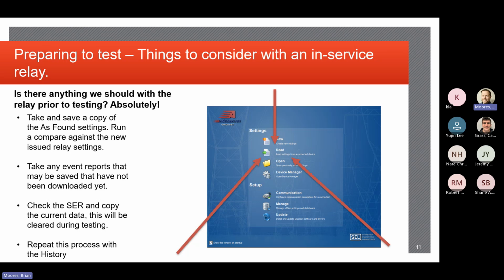The SER data is sort of line by line, text-based, if you will. GE is a little different because you have to use their graphic interface in their software. But it's an element, a relay word bit, bit by bit with a timestamp. So whether input 101 turned on or output 101 closed, or whether it established the 3PT for three-pole trip, whatever happens to be set in that SER, it will be in a line by line and in order of how it operated as far as the relay saw it, usually out to the millisecond.